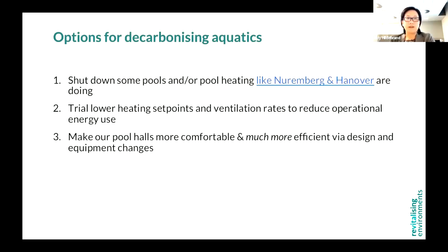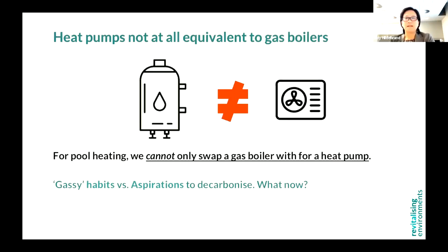The other option is to trial lower heating set points and lowering ventilation rates to reduce operational energy use. That won't remove all your issues, but you can at least see what the lower limits are if you have an existing building. And third is to make your pool halls more comfortable and much more efficient via design and equipment changes. Yes, you've heard heat pumps and boilers are not equivalent. You can't swap them over.